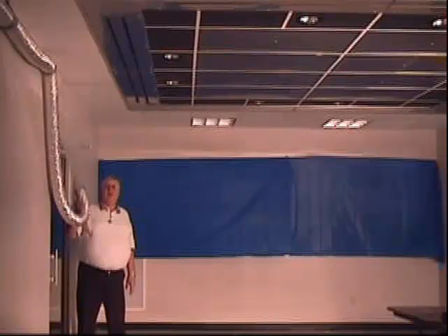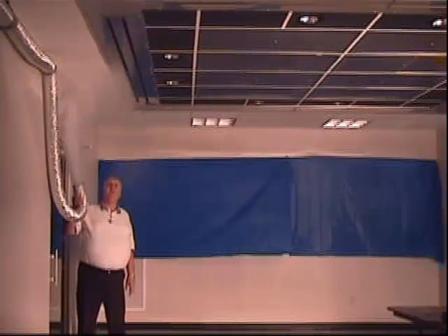This smoke demonstration shows that the smoke introduced into the room outside of the air curtain is not allowed to enter the sterile field surrounding the patient. Including the air curtain in the operating room suite design is the best way to ensure the safety of the patient during extended length or critical surgeries.